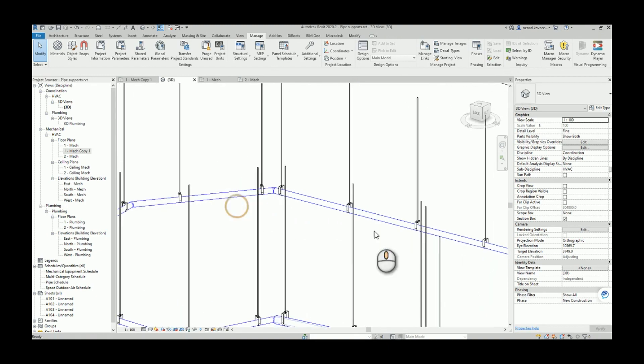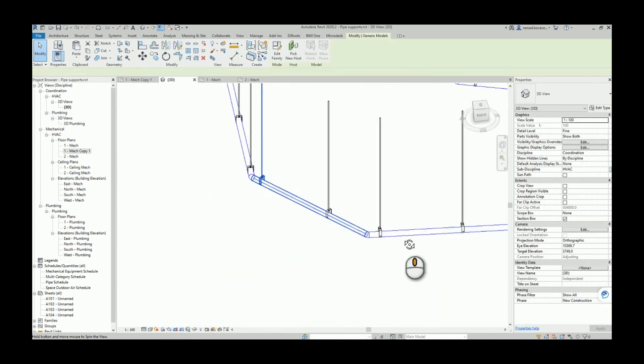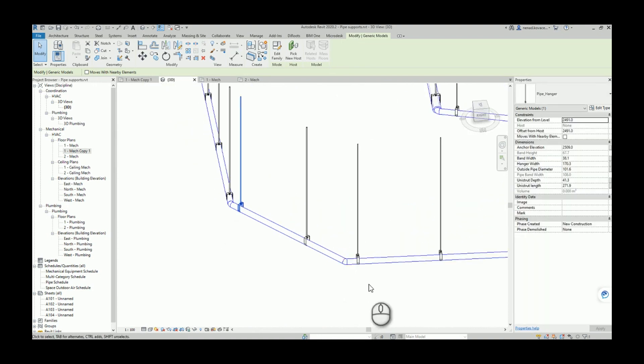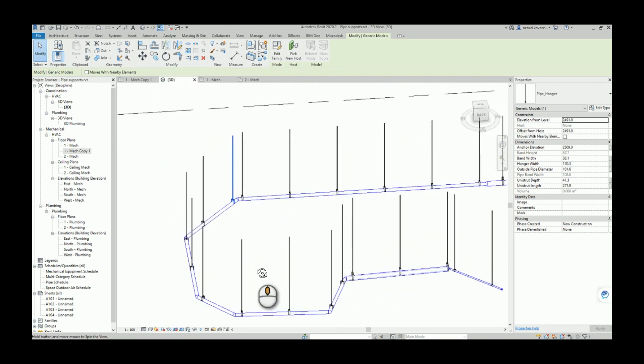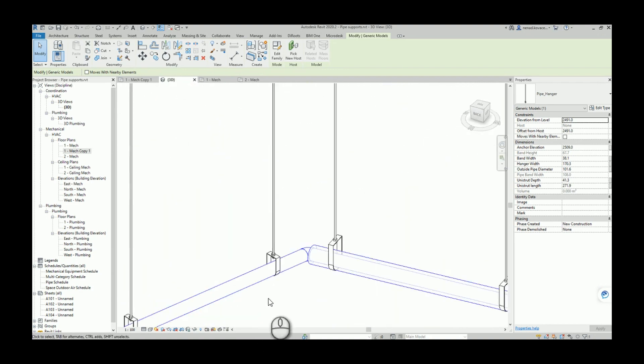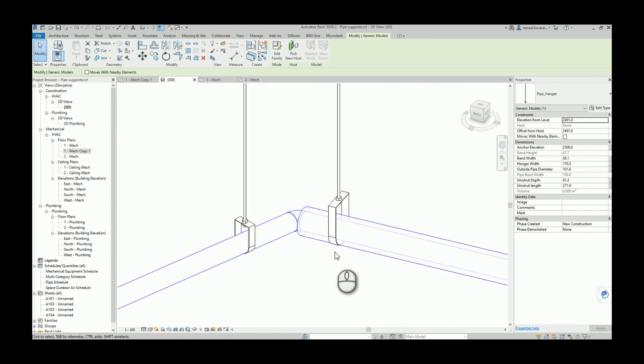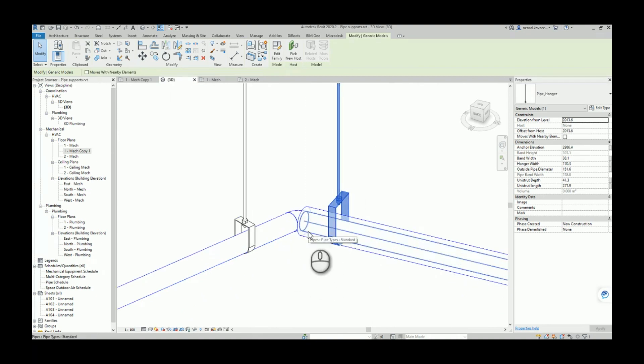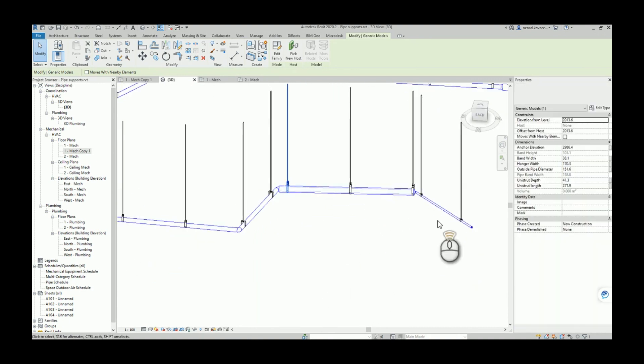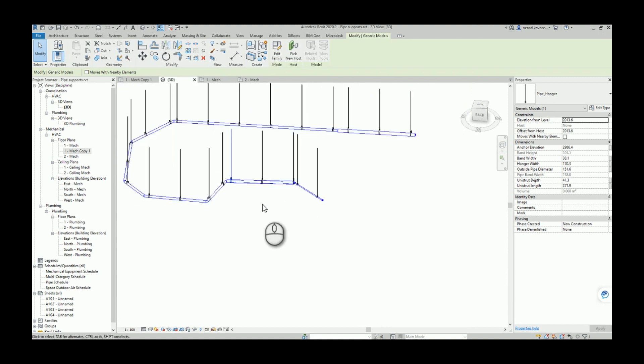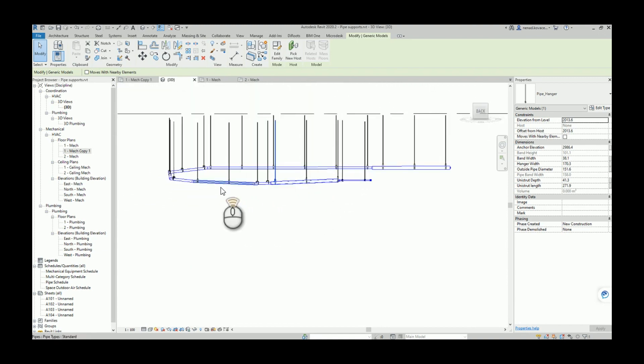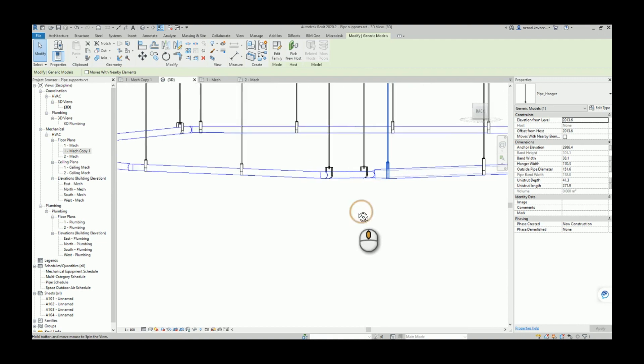Everything is okay — here when we have a 45-degree direction, everything is still okay, and here also. You can see that the hanger automatically adjusts not just the size of the pipe but also the thickness of the pipe insulation. At the end we have some reduction and a change of pipe direction — everything is okay. If we also take a look at the pipe slopes, it seems that everything is okay.